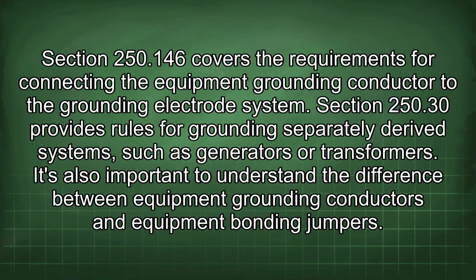Section 250.146 covers the requirements for connecting the equipment grounding conductor to the grounding electrode system. Section 250.30 provides rules for grounding separately derived systems such as generators or transformers. It's also important to understand the difference between equipment grounding conductors and equipment bonding jumpers.